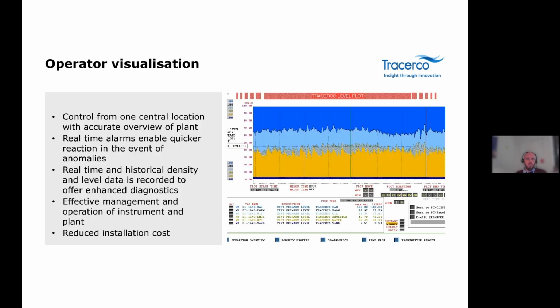So this is what an operator would typically see from the control room, and the screen can be seen from one central location or from the HMI, with an accurate overview of the plant status in real time. And these alarms allow for quicker reactions in the event of anomalies. The system can store both real-time and historic data, which is now able to offer enhanced diagnostics, remote calibrations, and better management of the vessel.